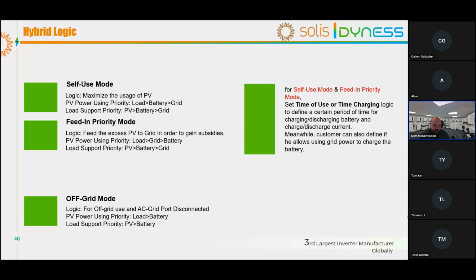The last mode we have is off-grid mode. What's hugely important to discuss is that you're putting all the loads on the inverter's backup port, so you need to consider the nameplate size of the inverter. Is it going to cover your loads? It also takes away the alarm message. In normal self-use, if the grid failed, your inverter would come up saying no AC grid. What the off-grid mode does is tell the inverter to ignore that. So that's the main difference. It just ignores the no AC grid alarm.